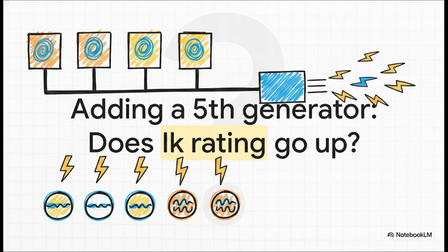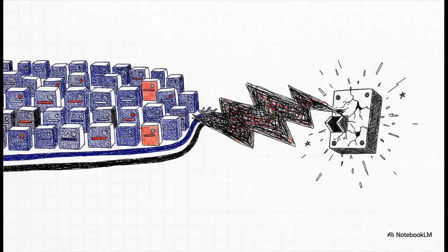Think about what we just talked about. Does the required breaker IK rating for the switchboard go up, does it go down, or does it stay exactly the same? I'll give you a second to lock in your answer. The answer is up. More sources on the bus always equals a higher required IK rating.